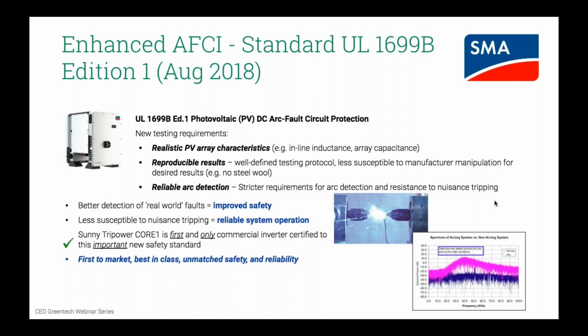And lastly, of course, what they wanted to ensure was that we were able to get reliable arc detection and interruption and make sure that we prevented additional fire hazards to the best of our ability, and also that we had resistance to nuisance tripping so that the system still operated reliably and didn't trip in situations where there really wasn't a fault. SMA, with the Sunny Tri-Power Core 1, was the first and still, we believe, the only commercial inverter certified to this new standard. So with the Core 1, you get improved safety and reliable system operation that you can't get with any other product.